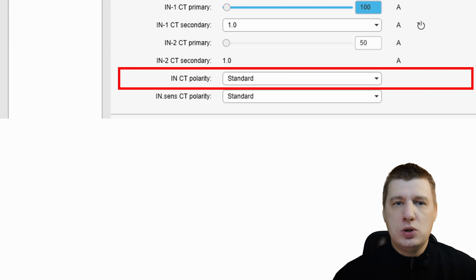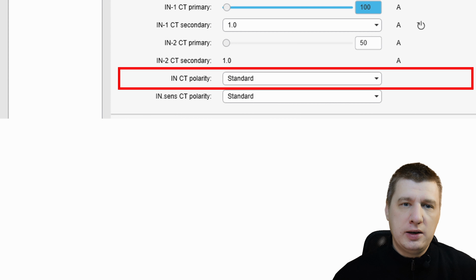What if the CT was wired backwards and it's too late to change the physical cables? The P5 has a software fix called angle offset. You can manually rotate the tripping zone from -180 to +180 degrees. Because it's so easy to get the wires swapped, it is mandatory to perform a primary injection test during commissioning. You must verify the angles on the relay against the known power flow to ensure correct polarity.